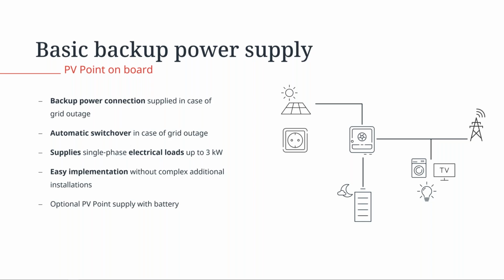So in our system itself, we have then lost our grid reference. We are then pulling full PV generation through our PV modules, through the inverter, and then out directly into our PV point. We can then also use our sun generation, or PV generation, to help supply our battery, to help with the charging, as well as the discharging of the battery through the inverter to our PV point. So if our sun generation drops below that 3 kilowatts, we can then utilize the battery to help supply the PV point in case of emergencies.